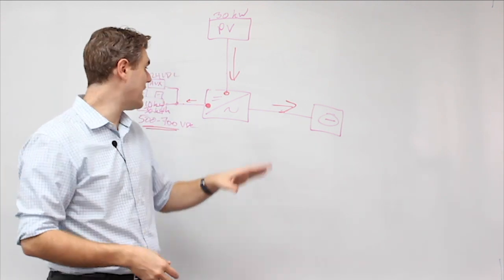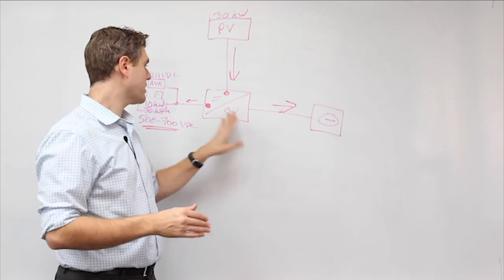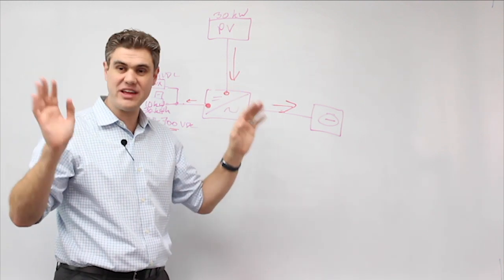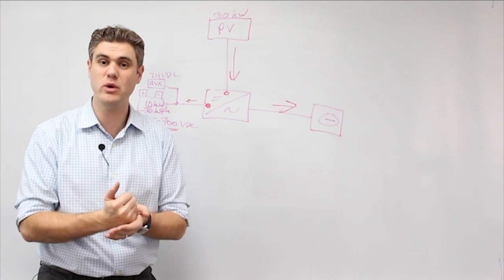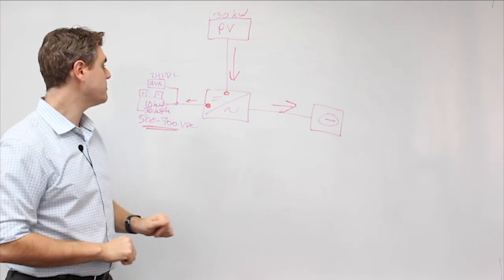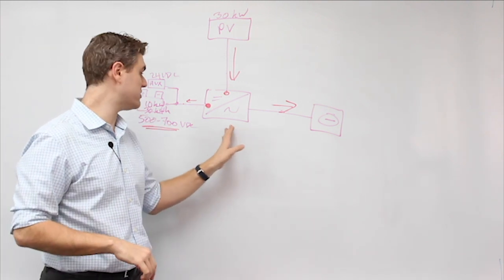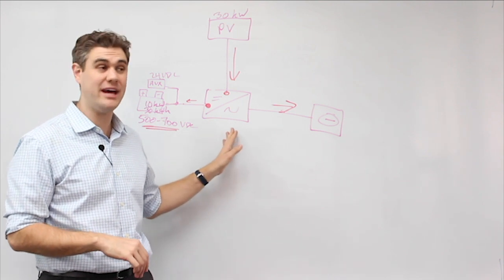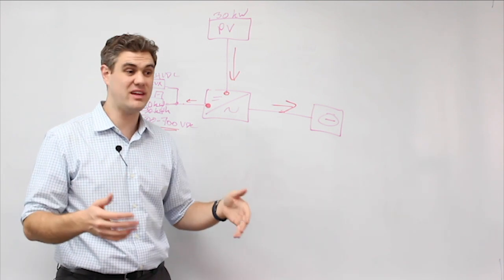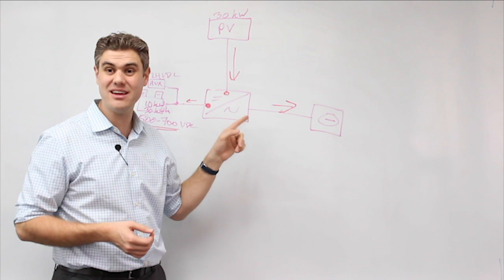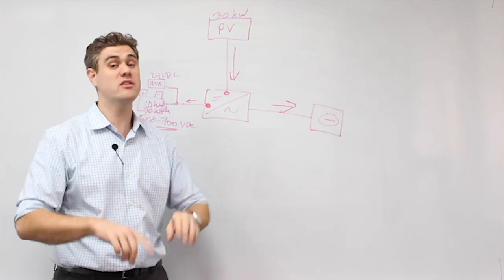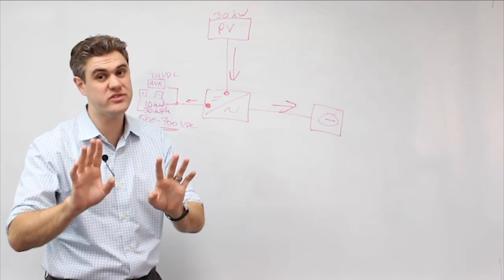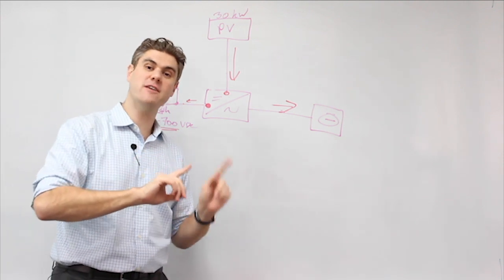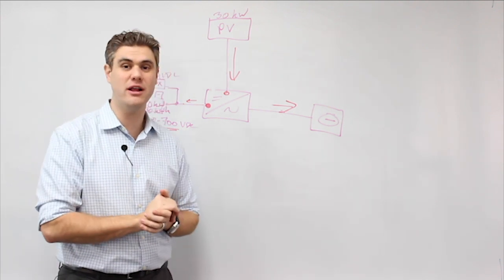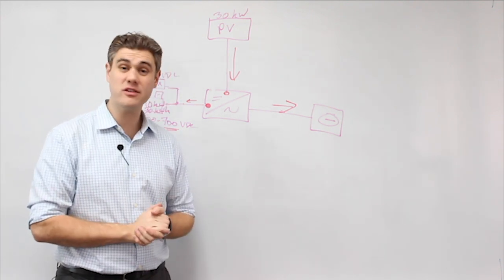It's something you can test in the lab and put a logo on, and utility companies, as long as it's got that sticker, trust that it's doing its job the way it was designed. And this is a UL verification process that is currently underway today. We've already had UL verify and witness test systems that do exactly this and put their logo on it. It's not a UL certification. There's no UL standard for this. It's a UL verification, a separate service that UL offers, and utilities are accepting it.